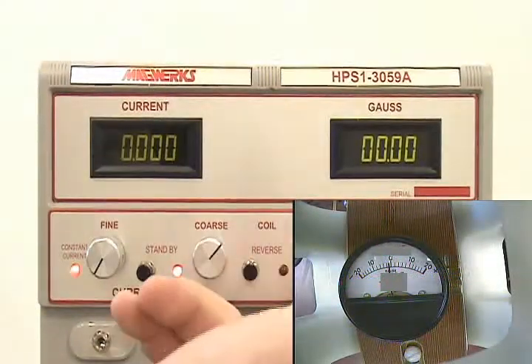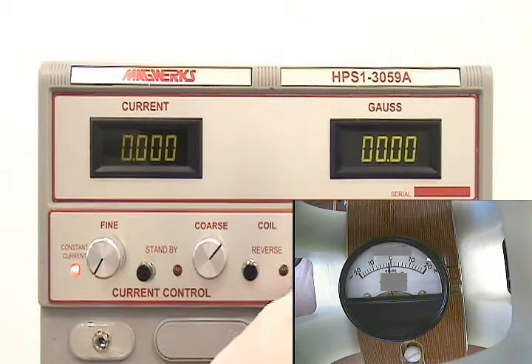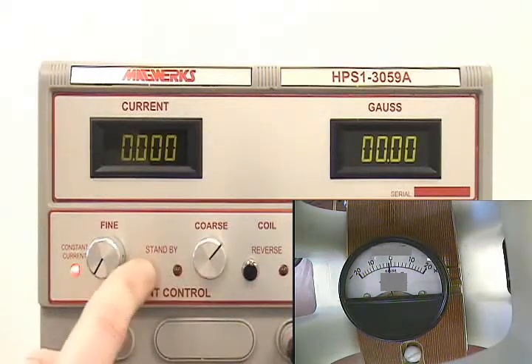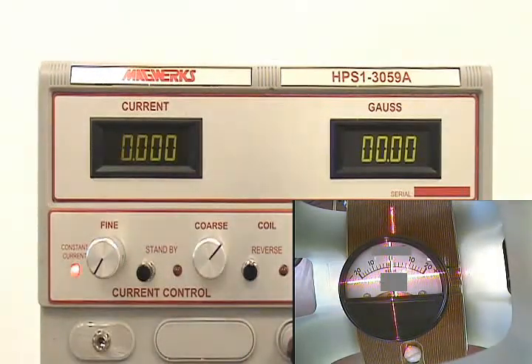First we test the system in automatic mode and see what happens. When the system is in automatic mode the laser comes on again so we can verify the meter is properly aligned before recording the results.